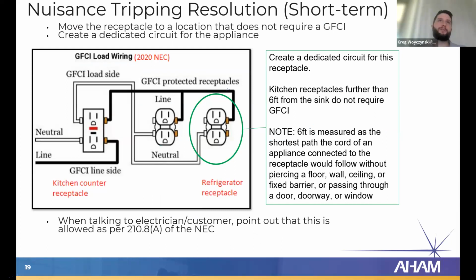So another short-term solution to GFCI nuisance tripping is to move the receptacle to a location that does not require a GFCI. So for example, if you have a receptacle that's within 6 feet of a sink that's connected to a GFCI breaker, you can move that receptacle just 2 feet down the wall, work with an electrician to do that if you're not qualified yourself.